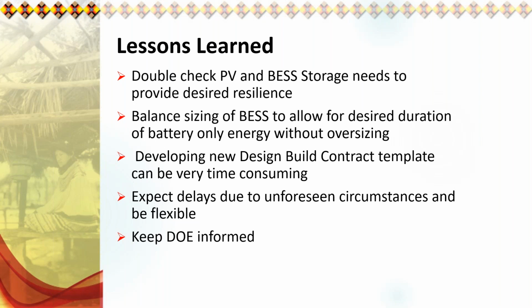So, lessons learned. I've already mentioned some of this, but the first thing you need to do is double check your PV and BESS storage needs to provide the desired resilience. In the original concept given by a consultant, we would only have received about 15 to 30 minutes of runtime for the facility with the amount of BESS storage proposed. We went back to Baker Tilly, and they resized and reanalyzed the needs of the building and came up with the proper sizing. After that, we were able to go back, explain the situation to DOE, and modify our grant.